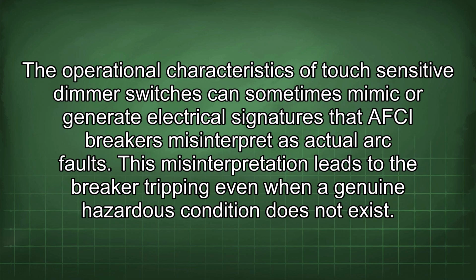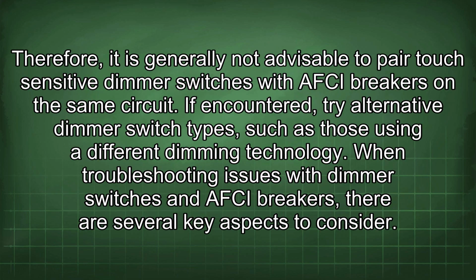The operational characteristics of touch-sensitive dimmer switches can sometimes mimic or generate electrical signatures that AFCI breakers misinterpret as actual arc faults. This misinterpretation leads to the breaker tripping even when a genuine hazardous condition does not exist. Therefore, it is generally not advisable to pair touch-sensitive dimmer switches with AFCI breakers on the same circuit. If encountered, try alternative dimmer switch types, such as those using a different dimming technology.